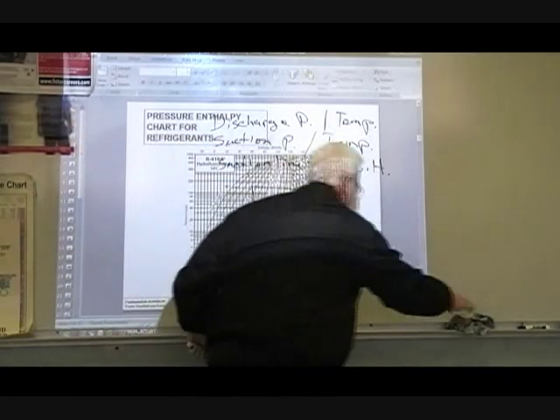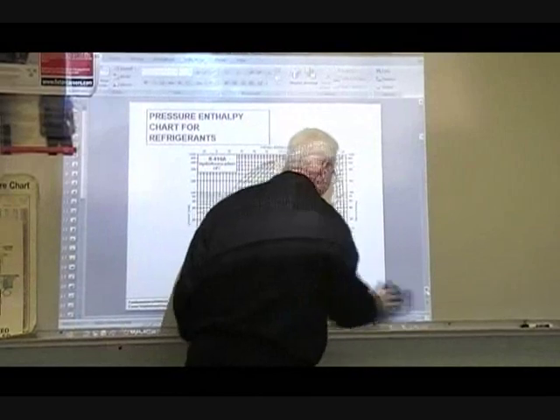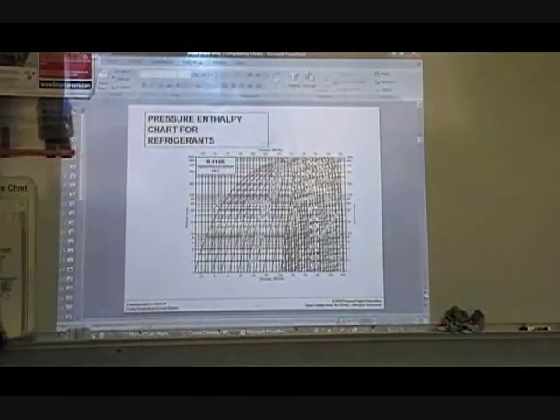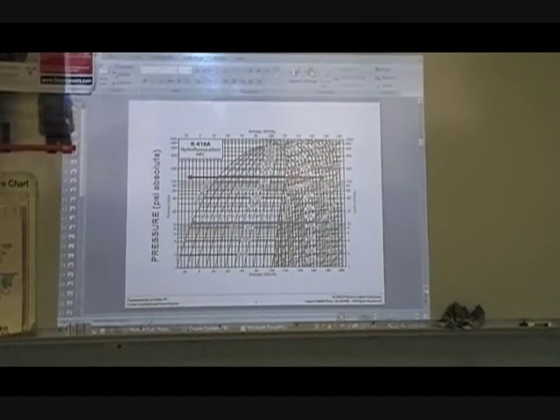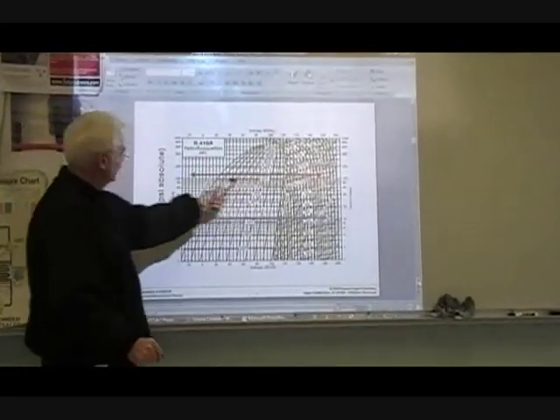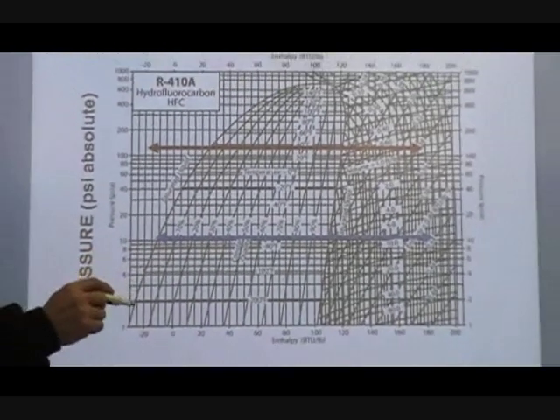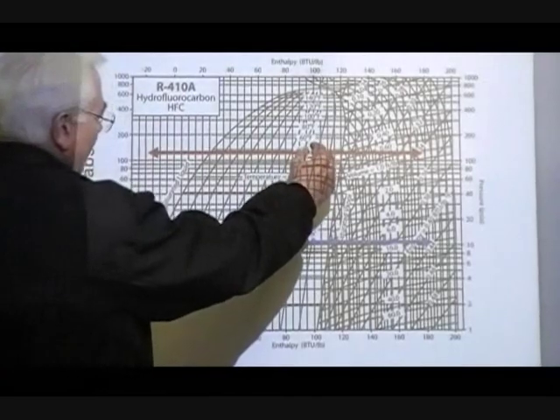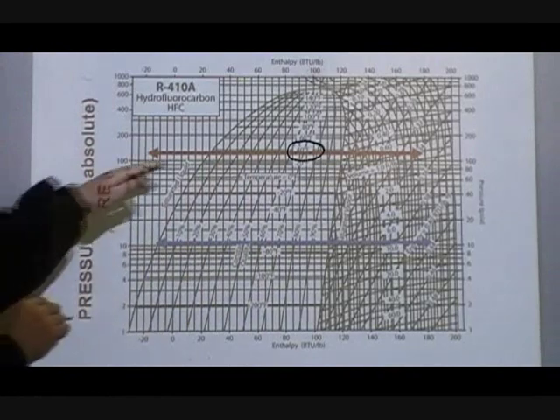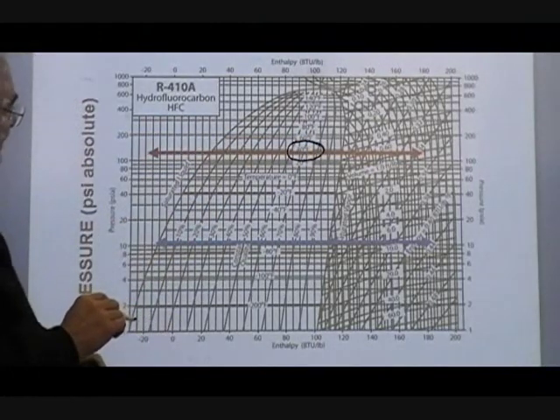When you have that information, you can actually plot these things on the pressure-enthalpy diagram. Moving on — this next slide is just showing pressure in PSI absolute and temperature scales. Keep in mind that most air conditioning systems and comfort cooling will have an evaporator operating temperature of about 40 degrees. That line is where we come in and look at what's going on inside that system. If you have a medium or low temperature machine with an evaporator operating temperature of minus 20 degrees, your box will be down in that lower region.